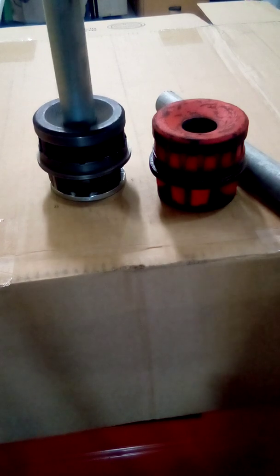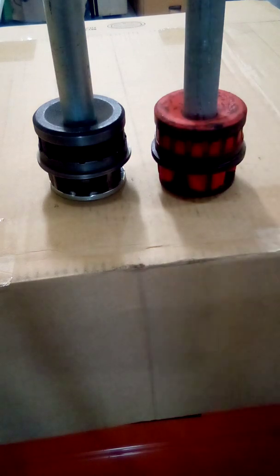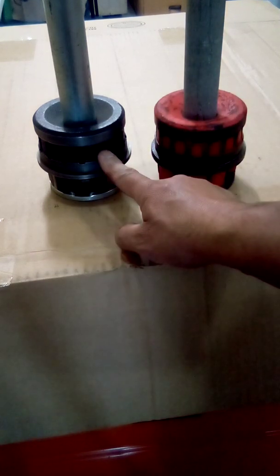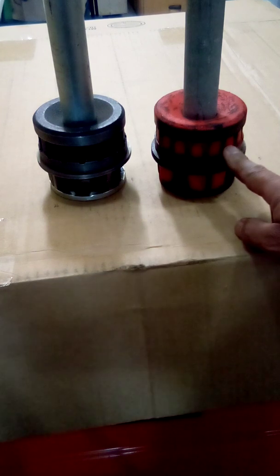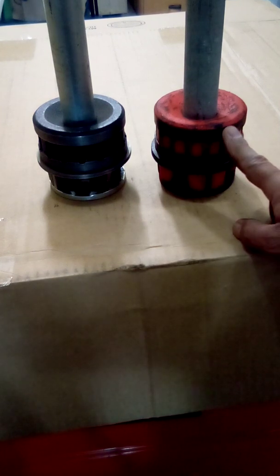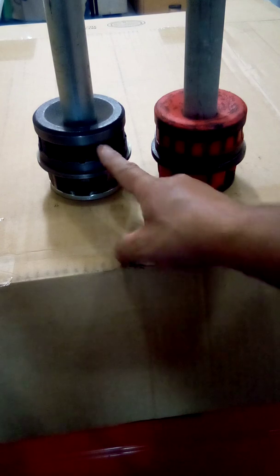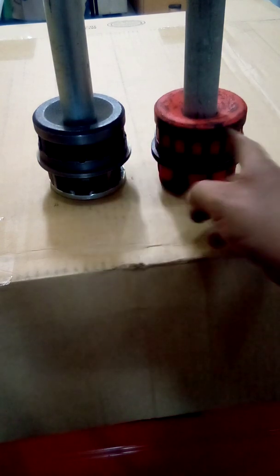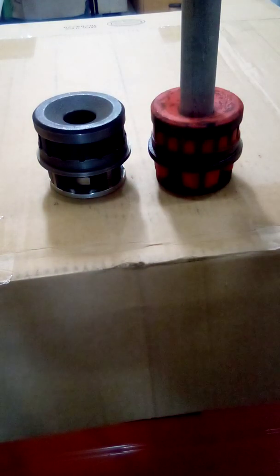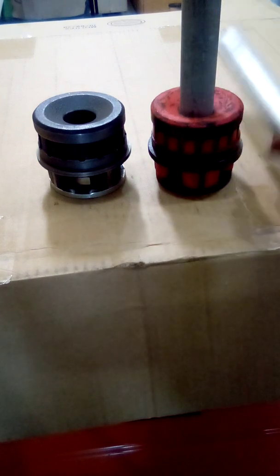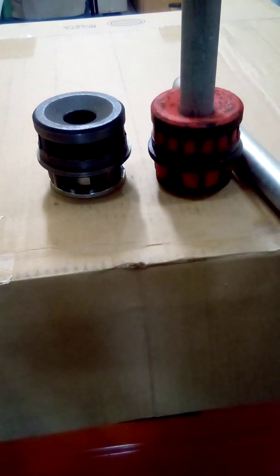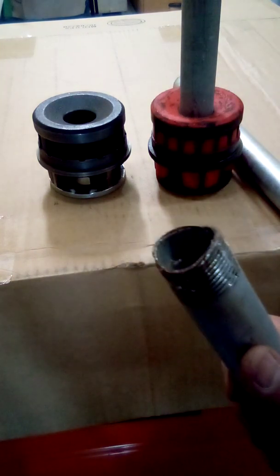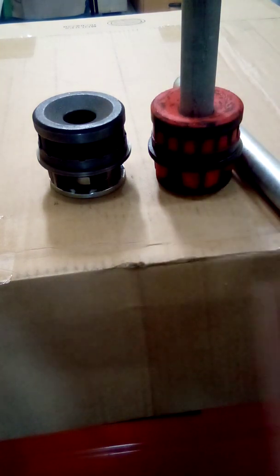So yeah, that's the difference. A lot of people don't talk about it. IMC, RMC, okay, rigid. So there's two different dies, two different conduits. This one will go in there and cause it to collapse. This one won't go in here.